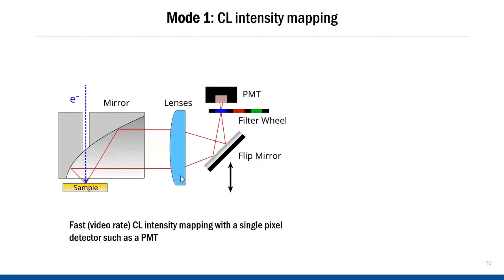The first imaging mode that I'm going to describe is intensity mapping. In this mode, you raster scan the beam over the sample, and for every point, you collect the CL with a single pixel detector, a photomultiplier tube. You can have a filter wheel in front of the PMT. So then you could collect all the wavelengths by not filtering at all, which is panchromatic imaging, or you can use the filter wheel and do some coarse filtering to get some wavelength information. During the raster scan, you would fix the wavelength, collect CL for every point, then change the wheel position and do the same again. For your reference, this is the sample, this is the parabolic mirror, and this is the primary electron beam of the SEM. The CL that's generated here is focused using the mirror and lenses, sent to the flip mirror and then sent to the PMT with or without a filter wheel in between.